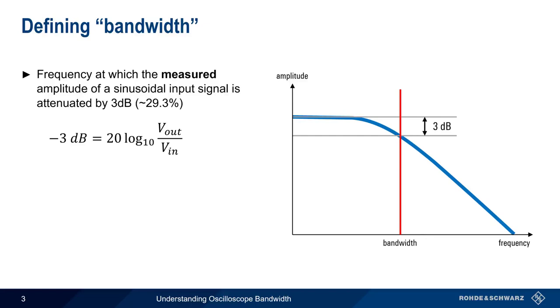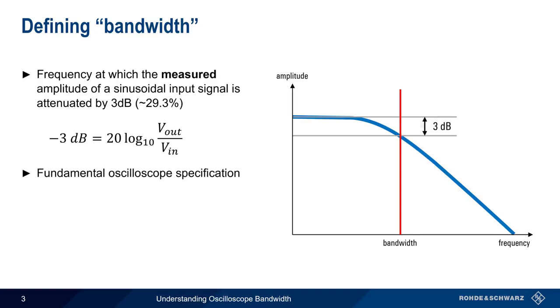The bandwidth of an oscilloscope is defined as the frequency at which the measured amplitude of a sinusoidal input signal is decreased or attenuated by 3 dB. This is the same as an amplitude reduction of about 30%. Note that even at frequencies within the scope's nominal bandwidth, measured signal amplitude may still be lower than the actual amplitude. Also note that even at frequencies above or outside of the scope's bandwidth, measurements are still possible, although amplitude accuracy might be quite low.